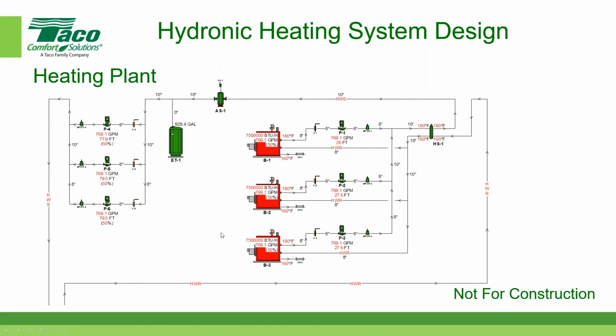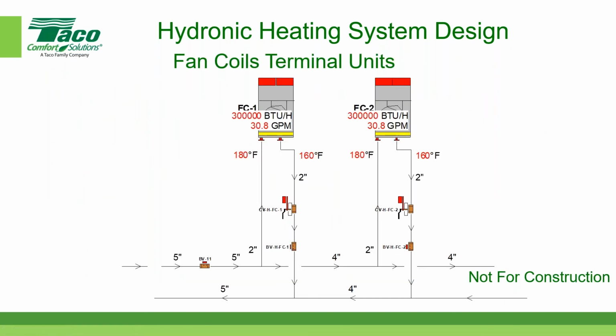Okay, so that's the boiler plant. Let's take a little bit closer look now at the terminal device. So in this case, we have two terminal devices. Each one is 300,000 BTUs per hour. And down here, we can see the supply piping that came from the vertical main. So there's the 5-inch supply. Excuse me. And we're tapping off of that supply. The secondary pumps are providing the pressure in order to overcome the resistance. And there's the terminal device.